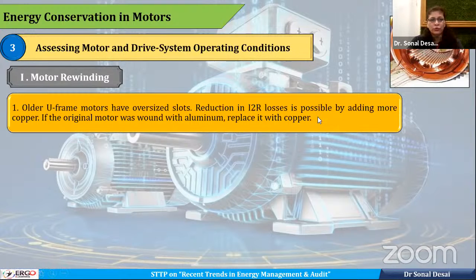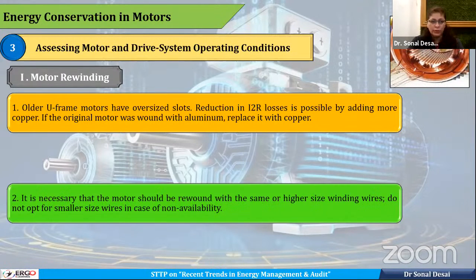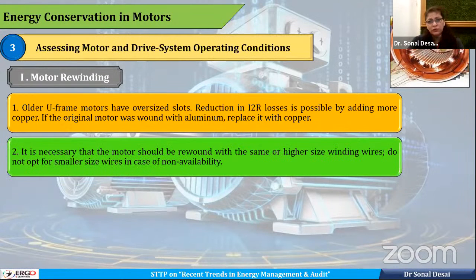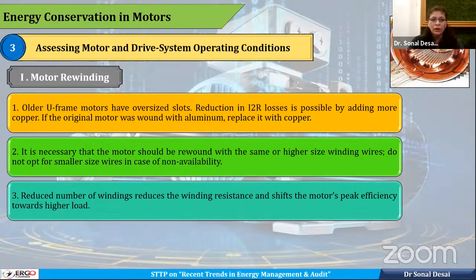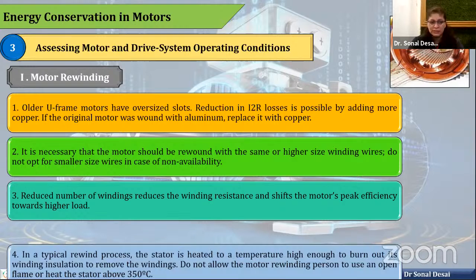If there is an older U-frame motor which has oversized slot, it will have reduction in I²R losses. Add more copper to that, so that will reduce those losses. And if the original motor was wound with aluminum, then replace it with copper. If it is necessary that we have to rewind the motor, then go with the higher size wire rather than reducing the size of the wire. Then reduced number of windings will also have reduced winding resistance. So motor's peak efficiency is directly related with the winding resistance.